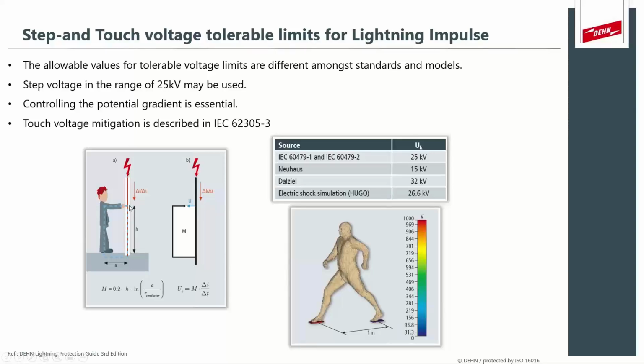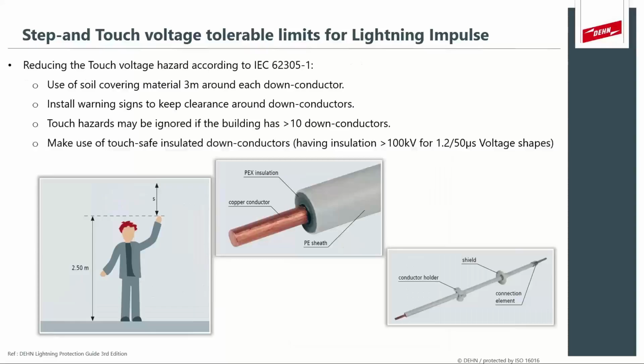The reason is that you create an inductive loop between yourself and the ground, and you are a conductive component, and lightning will actually flash through the insulation due to this mutual inductance loop. Now, the ways to mitigate touch voltage are directly described in IEC 62305 Part 3, the lightning protection standard. It says you can ensure that soil covering material is applied with a 3-meter radius around the down conductors, and that a 3-meter radius of clearance is kept around down conductors.